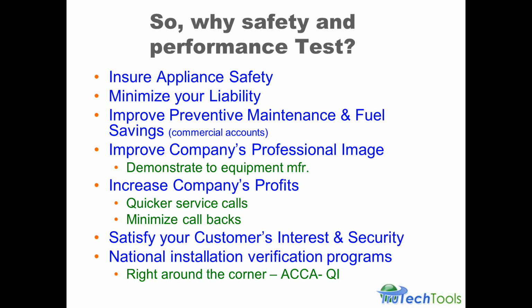Doing a tune-up or checking how the equipment is running can assist you in preventative maintenance activities, which will help with fuel savings. And this is especially true for commercial accounts where there's higher BTUs, higher fuel consumption rates. But even in residential, having a preventative maintenance check with a combustion analyzer can tell you loads of information about how the equipment's running.